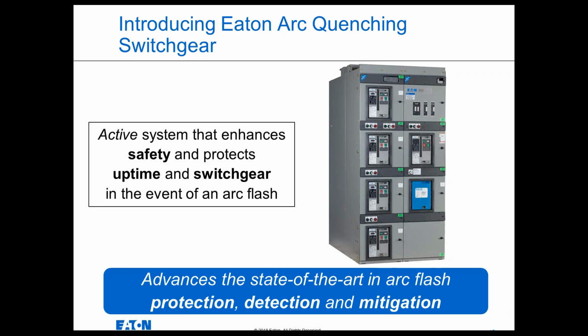to the drawing board, and what we did is we developed a technology that really tried to ameliorate all of these shortcomings of arc resistant, arc detection, energy reducing maintenance, which is ZSI, using a breaker to clear the system, et cetera. That would address all those shortcomings in a singular product that would really make equipment safer to be around. So what our engineers came up with is what we call Arc Quenching Switchgear.